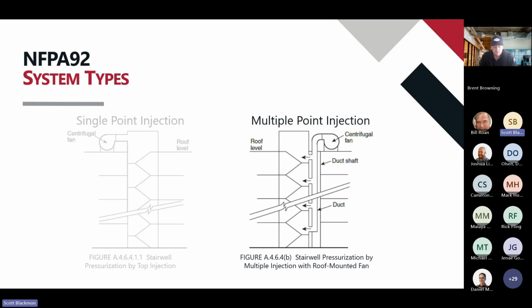The other type is a multiple point injection system, and this is really what NFPA pushes towards for all buildings. That's where you've got a fan that dumps into a duct that's either adjacent to or in the stairwell, and that duct injects air at multiple points in the stairwell. NFPA allows you to do up to 3 floors per injection point.